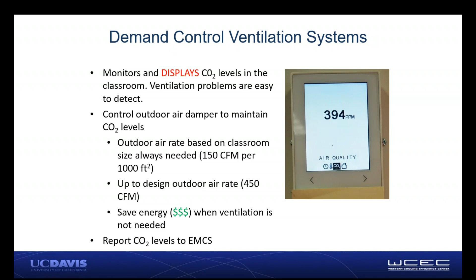The other thing you can do is control your outdoor air damper to respond to the CO2 level, which is a next step. You still have to maintain some minimum ventilation all the time, but you can save energy when ventilation isn't needed. So when the kids go to lunch, the damper can close slightly if CO2 is low, or if they're at an assembly, or maybe the control system wasn't programmed correctly and it's running on a school holiday or teacher work day when there's only a couple people in the classroom. This enables a lot of functionality.